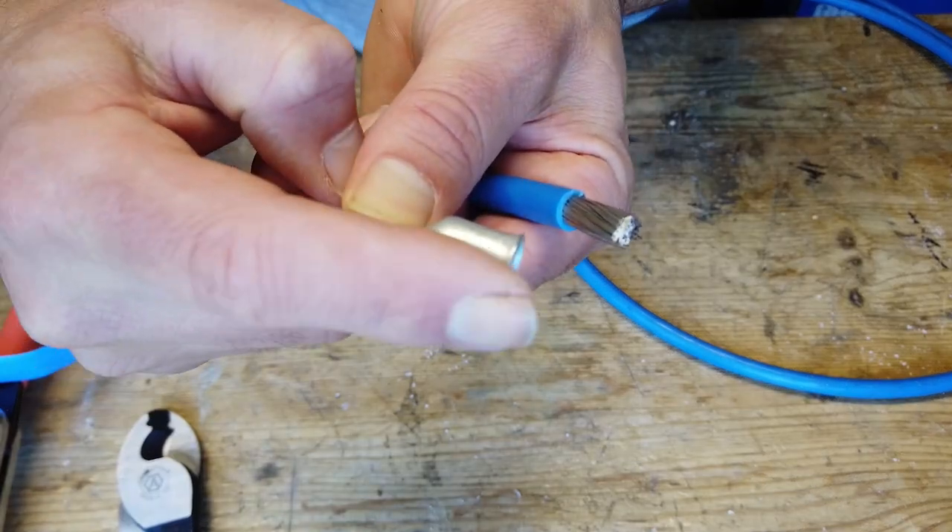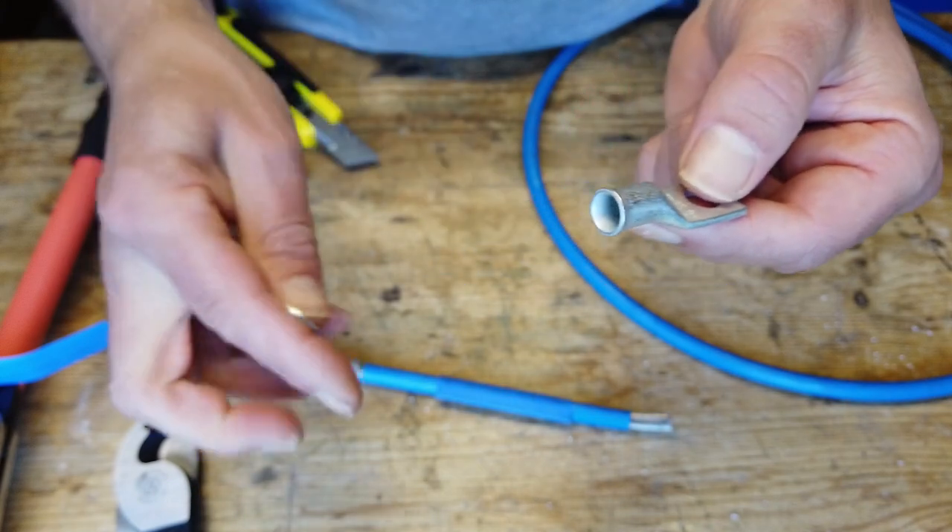Perfect, this is the high-quality connector. As you can see this little bow, and this helps you to get all the strands in the connector. These are two models, they're both for 25 square millimeter. Of course this is the cheaper one, the weight I think it's ratio 1 to 3, and you see they are much thicker. So if you want to go serious, you want to use lots of power, make sure you go for the high quality connectors.